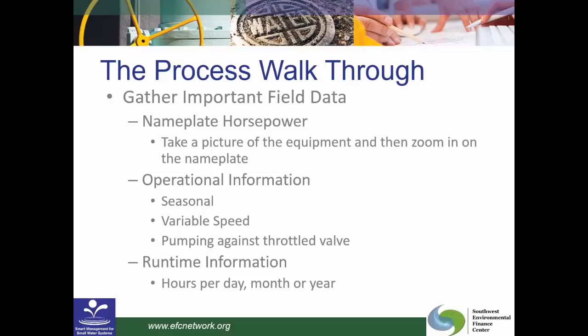Also, you want to make sure that you understand runtime information for each asset. So how many hours per day is it running, or how many hours per month or year is that pump running? So there are different ways to gather that information. Sometimes we're recording it on daily log sheets. Sometimes we know that when the well turns on, the chlorine pump turns on. So if we have runtime records for the well, we can essentially assume the same runtime records for the chlorine pump. So different ways to gather that information, but oftentimes talking to the person that runs it is the best way to get a feel for how often each day that pump or motor is running.